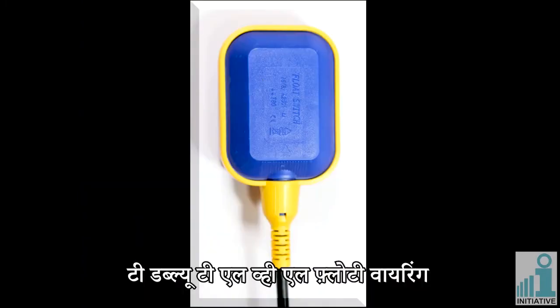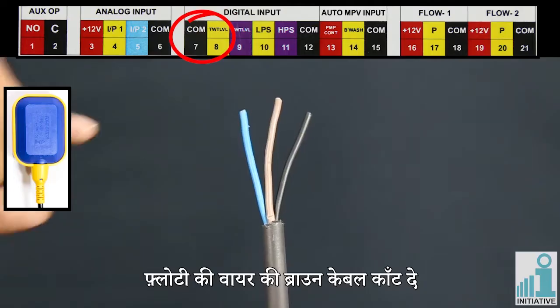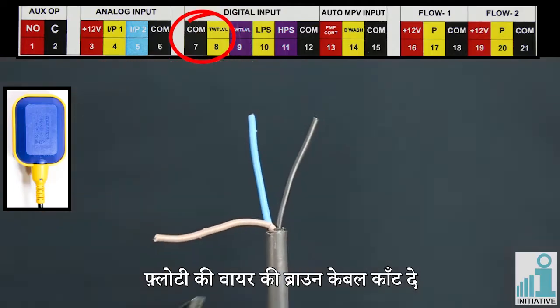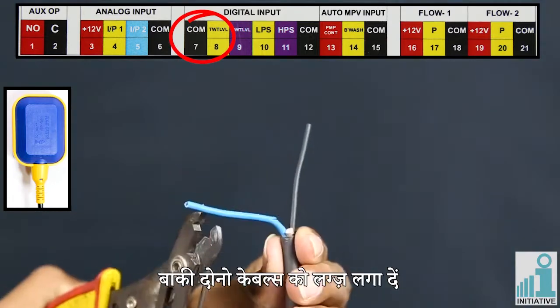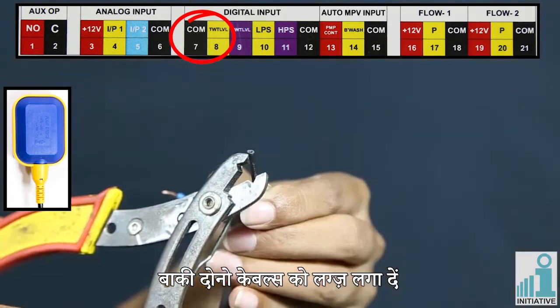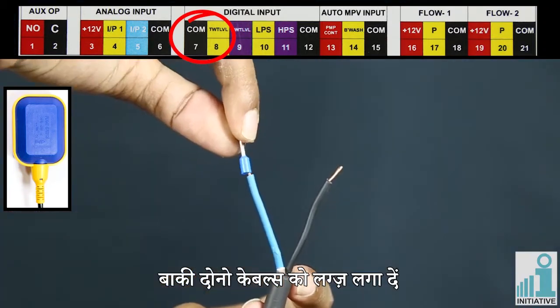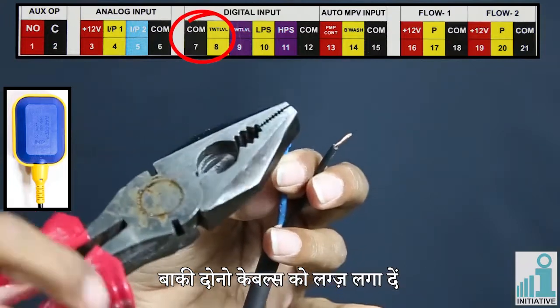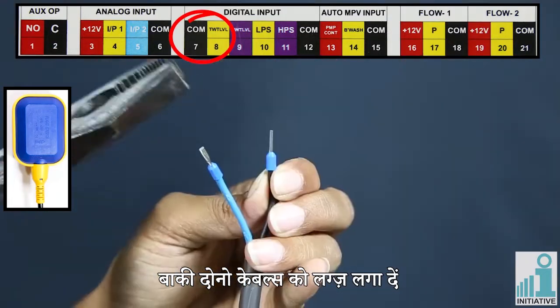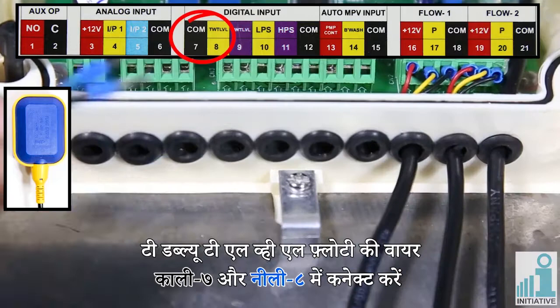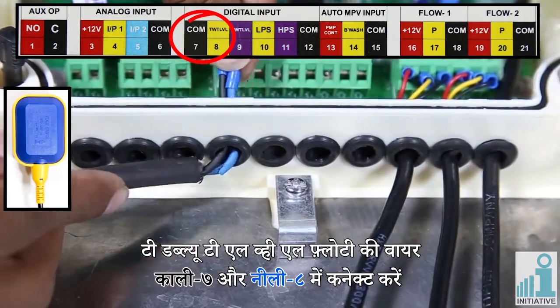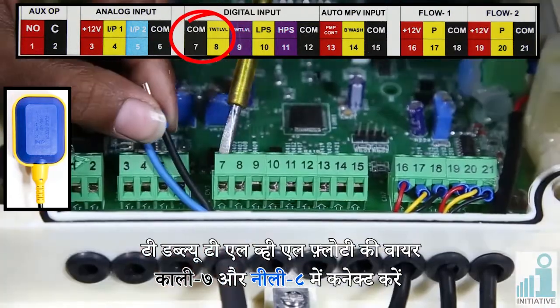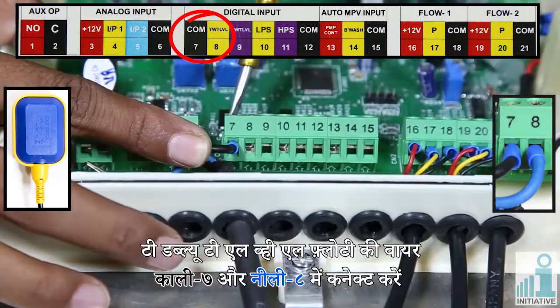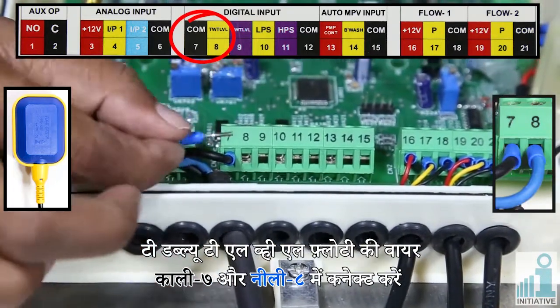TWT LVL Floaty Wiring. Cut the brown cable of floaty wire. Fix the lugs on both the remaining cables. Connect TWT LVL Floaty wires black in 7 and blue in 8 number connector.